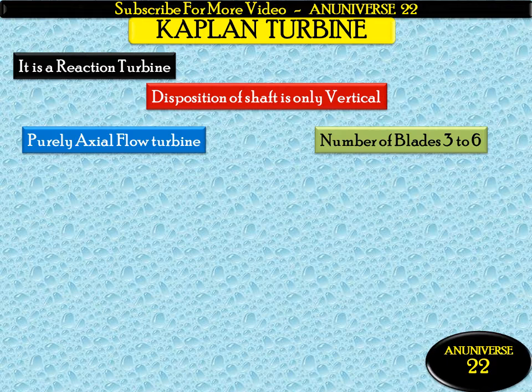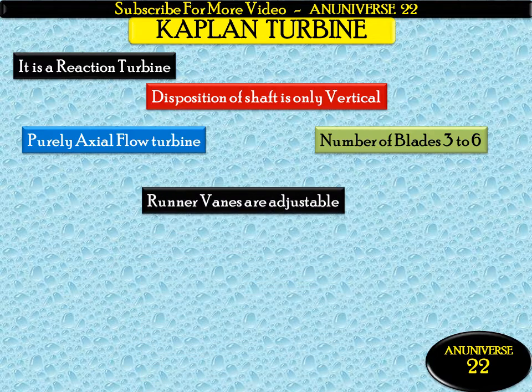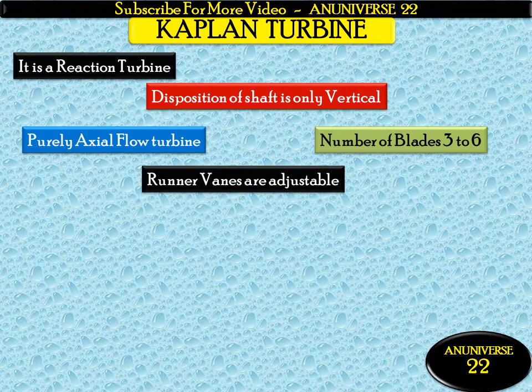Blades are made up of stainless steel and mounted on the hub. Runner vanes are adjustable. If vanes are not adjustable and they are fixed on the hub, that is the propeller turbine. But in the case of the Kaplan turbine, runner vanes are adjustable.